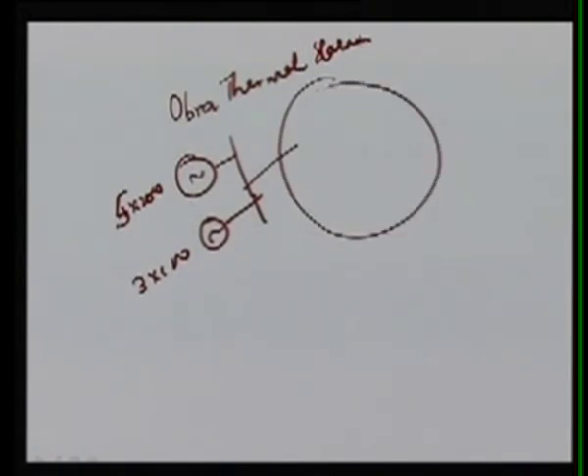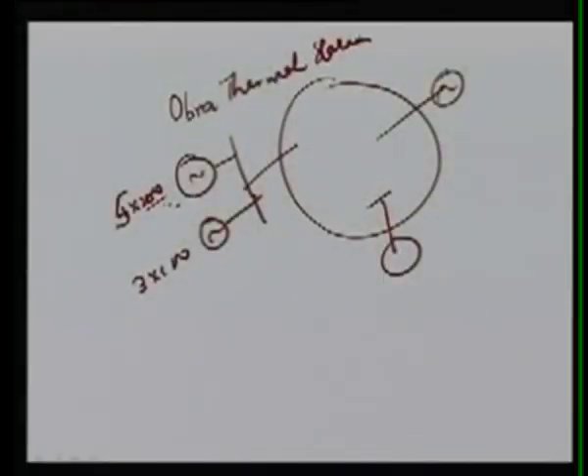What happens? We have other generators here in the system, more than 40-50 generators in the NRB region. So if any one of the units at Obra is oscillating with respect to the other system, you can take this system as a standstill and see the oscillation in any unit of Obra - then we can say it is a local mode oscillation.